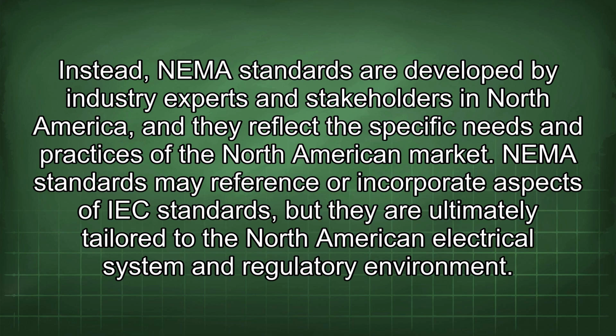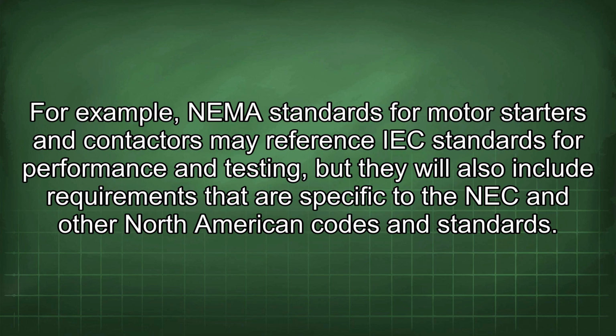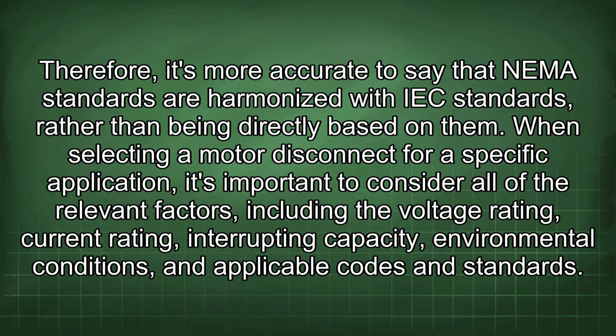NEMA standards may reference or incorporate aspects of IEC standards, but they are ultimately tailored to the North American electrical system and regulatory environment. For example, NEMA standards for motor starters and contactors may reference IEC standards for performance and testing, but they will also include requirements that are specific to the NEC and other North American codes and standards. Therefore, it's more accurate to say that NEMA standards are harmonized with IEC standards rather than being directly based on them.